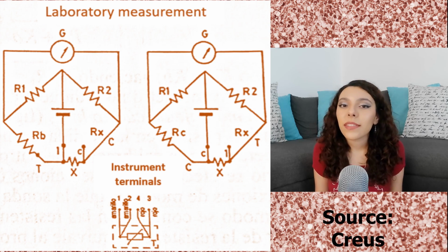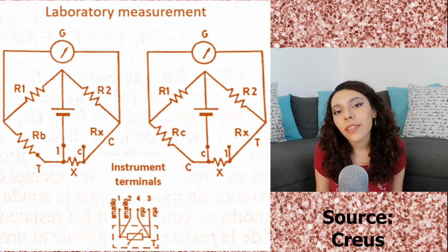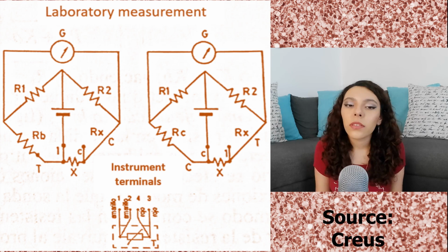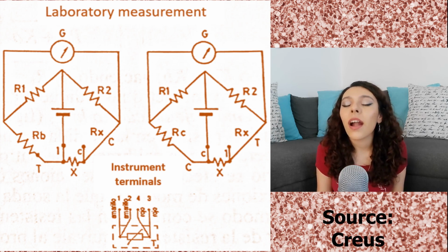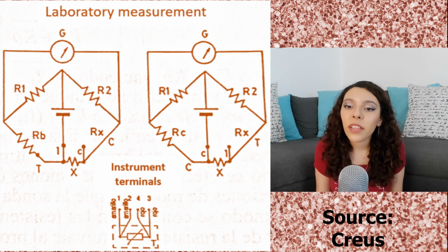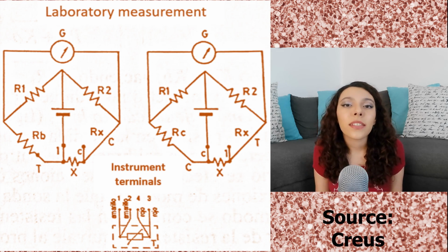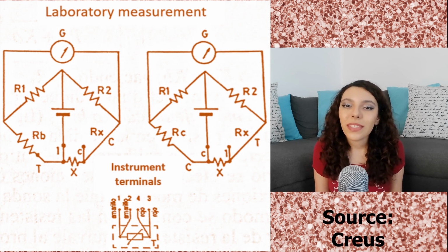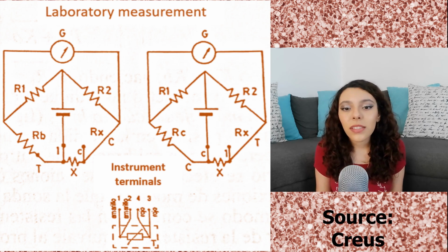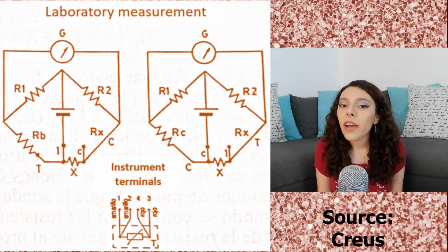The 4-wire assembly is used to obtain the highest possible precision in measurement, as is the case with digital temperature converters or the calibration of resistance standards in the laboratory. 2 measurements of probe resistance are made in the laboratory by combining the connections so that the probe passes from one arm of the bridge to the adjacent arm. Thus, the uneven resistances of the connecting wires are compensated, and the resistance value is equal to the average of the values determined in the 2 measurements.